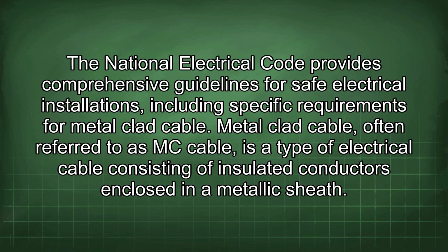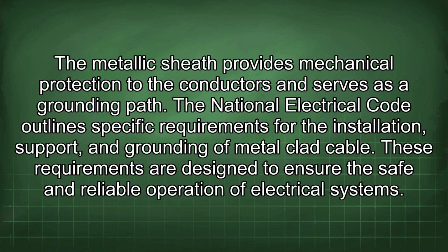The National Electrical Code provides comprehensive guidelines for safe electrical installations, including specific requirements for metal-clad cable. Metal-clad cable, often referred to as MC cable, is a type of electrical cable consisting of insulated conductors enclosed in a metallic sheath. The metallic sheath provides mechanical protection to the conductors and serves as a grounding path. The National Electrical Code outlines specific requirements for the installation, support, and grounding of metal-clad cable. These requirements are designed to ensure the safe and reliable operation of electrical systems.